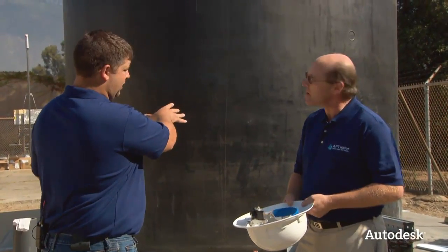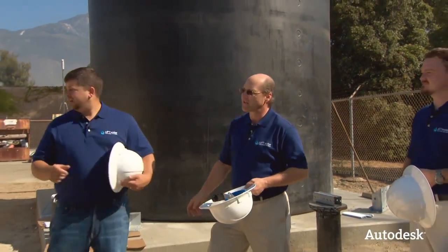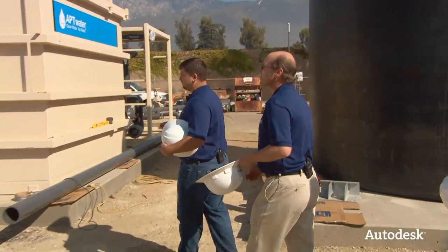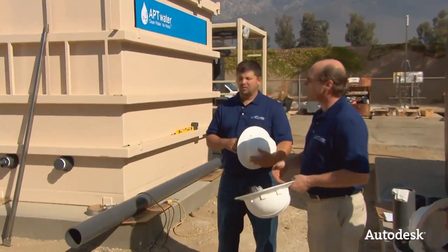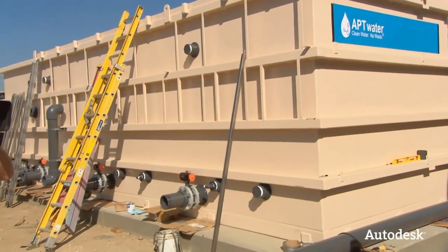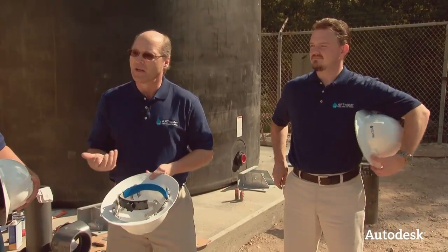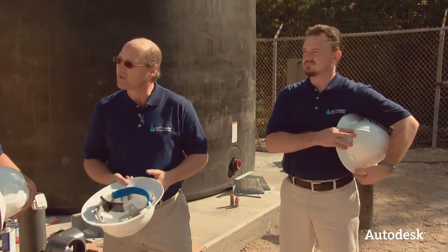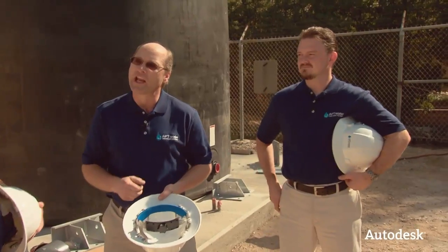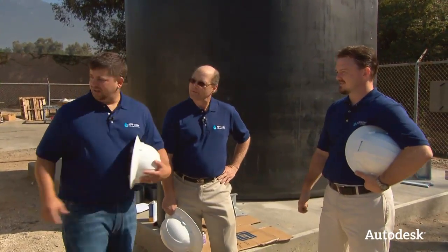After the nitrate's been removed... Where does that happen? It doesn't happen in here, right? No, that doesn't happen in here. That happens in the 3 basins that are inside of this large tank. The basins are filled with hollow fibers that the bacteria will grow on. After the nitrate's been removed, the bacteria will also remove the dissolved oxygen in the water, so we re-aerate the water. We bubble compressed air through it to re-oxygenate it. Then we filter it, remove turbidity and any traces of bacteria, and then disinfect it, and then it becomes drinking water.